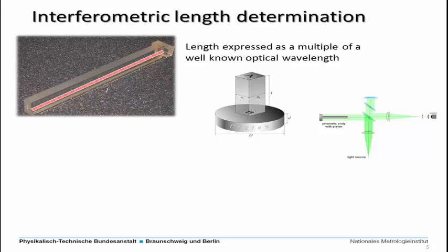So we use such an interferometer. Paul already showed you a sketch of this, but the main difference is that in his setup at NPL they use a laser, a point source from a laser, and we are using also a laser as a light source, but the laser light is divergent and then collimated, so that we are illuminating the sample under test in the whole field of view of the optics. The rest is similar to the setup which Paul has shown you in his talk.